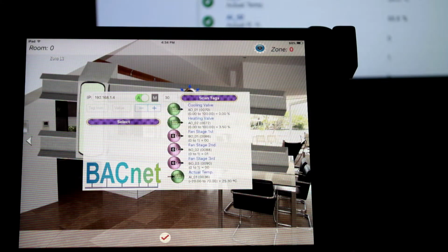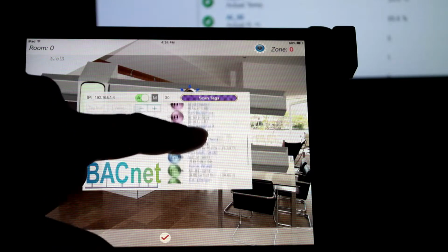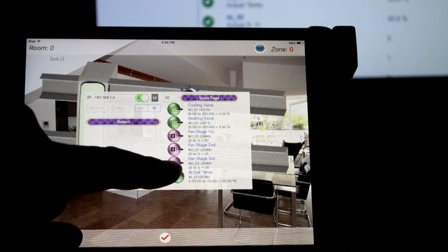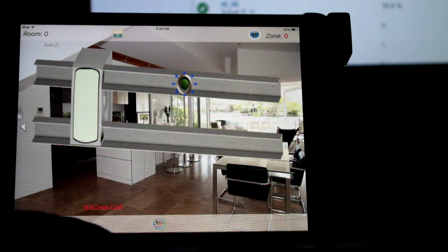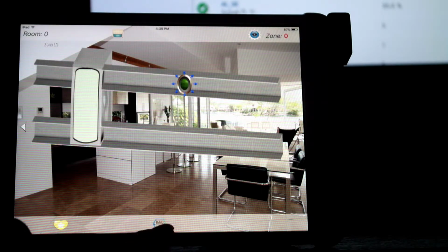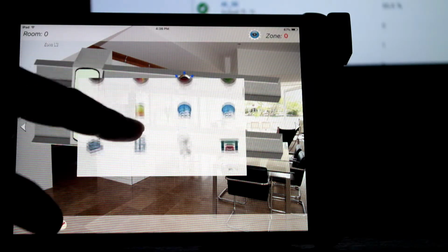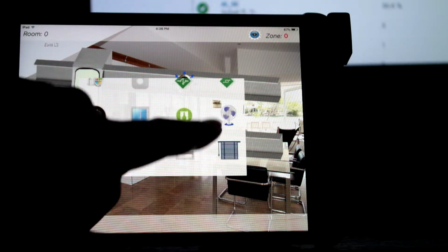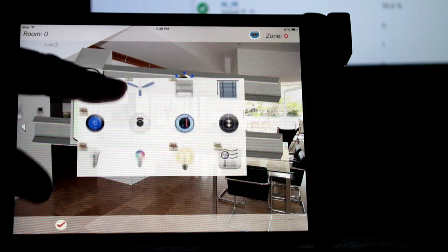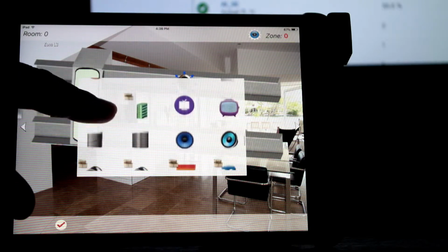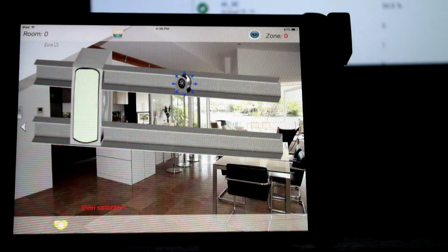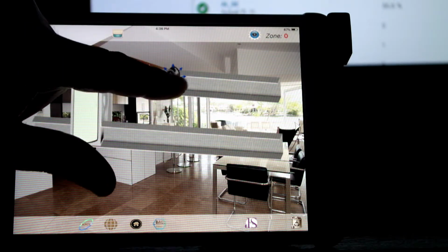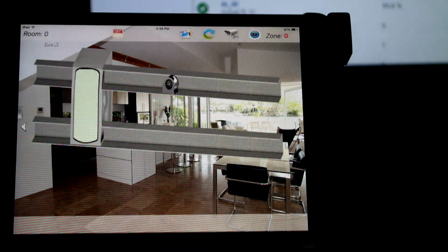Clicking scan tags will show the list of the control points or tags exactly as it shows on our web interface. So I click the fan multi-state tag. Click select and then the correct button below. This appearing icon looks like a yellow heart. It's for the favorite icons that I can choose from. So it shows many icons. I'm sure the fan is down there somewhere. Aha! Here it is, a fine suitable return air fan. Now click the correct button below and voila!